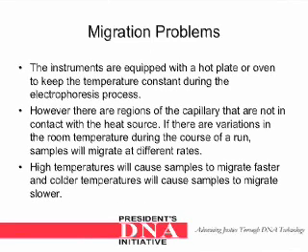The instruments are equipped with a hot plate or oven to keep the temperature constant during the electrophoresis process. However, there are regions of the capillary that are not in contact with the heat source. If there are variations in the room temperature during the course of a run, samples will migrate at different rates. High temperatures will cause samples to migrate faster, and colder temperatures will cause samples to migrate slower.